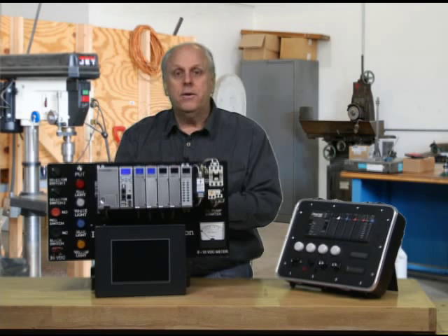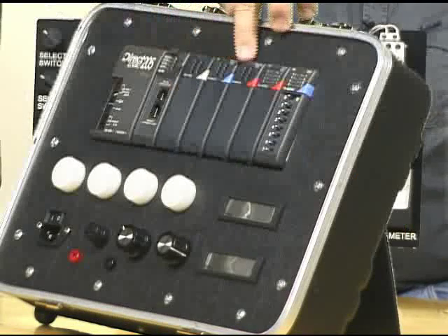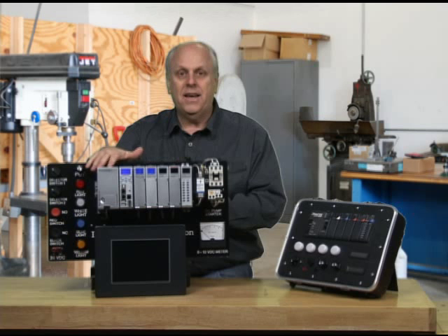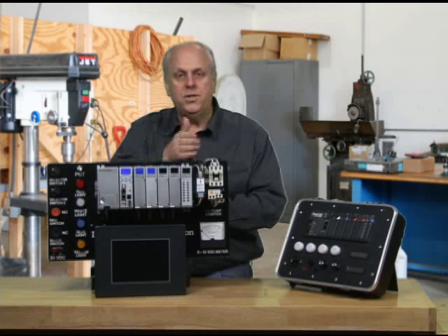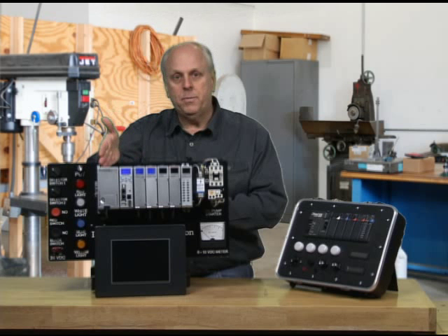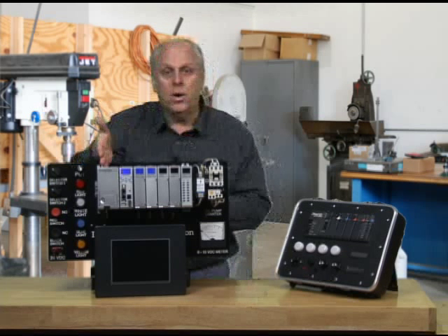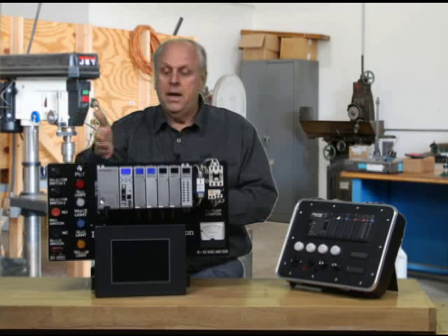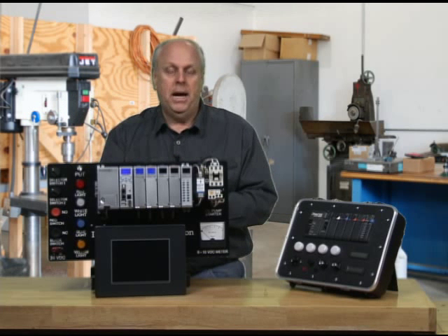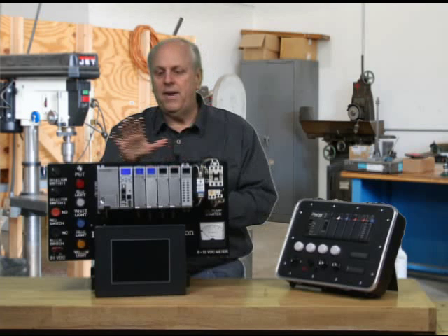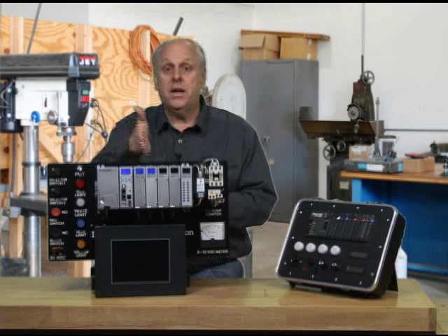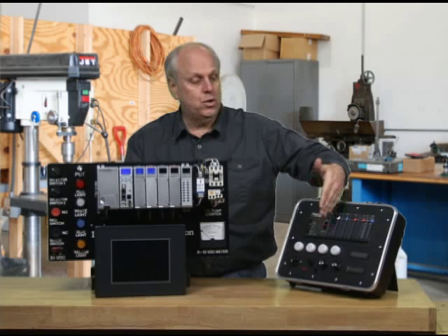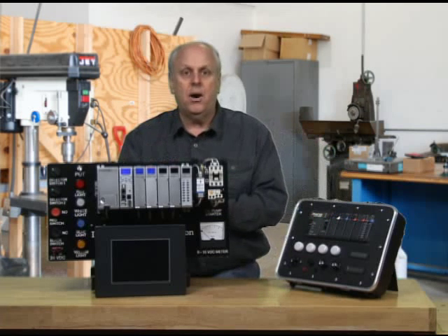When I put the rack together, in the older systems, I had to watch how many cards I put in because the power supply in there could only power up so many cards. This was designed with a power supply that can run any cards. It doesn't matter if I put all relay cards into this rack, I don't have to worry about what power supply I've purchased because I either buy a 120 volt power supply or a 24 volt power supply, and by the way, the 120 goes all the way up to 240, and the 24 goes all the way up to 48. So there's two power supplies I buy. I plug it in, and they power up the rack. Doesn't matter if I have all relay cards, it doesn't matter. And all the cards can go into any slot. On the older systems, certain cards had to go in slot 1. Certain cards had to go in slot 0, depending on what the card was.